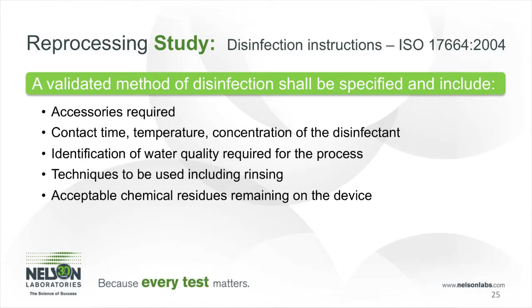We need to ensure that the water quality for the final rinse is of a critical water supply, since we are expecting these devices to be specified as disinfected after that stage of the reprocessing. And we also need to test to ensure that there is no cytotoxicity after the disinfection test, to ensure that all the disinfectant has been rinsed off the devices properly.